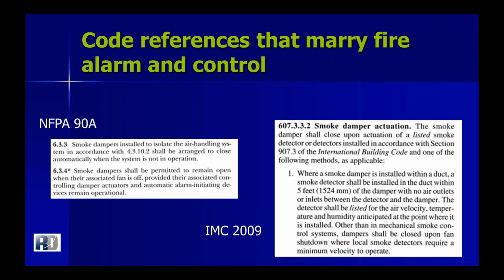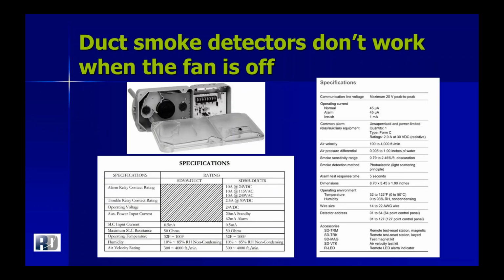So what we did, next page, Peggy, is quite simply just went to the main detection device that's providing the signal in the first place. And I searched for specifications on all sorts of them and pulled out a couple that I found here. And if you notice, both of these have air velocity readings, a minimum and a maximum. What's also interesting is that the ratings aren't even the same between them. One does have, I would say, a significantly lower feet per minute requirement. But the most important fact is that all of them have a minimum velocity.